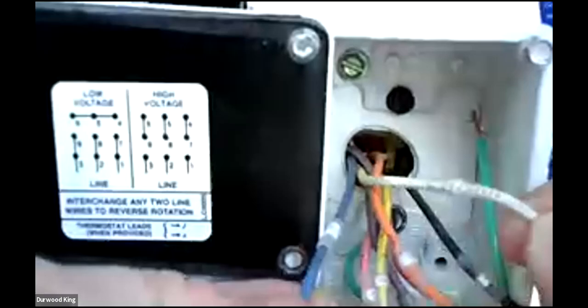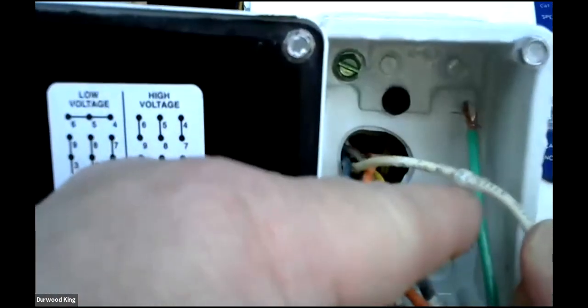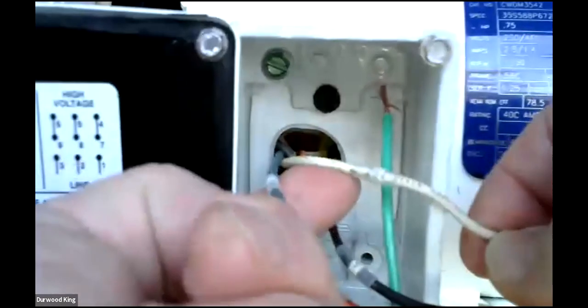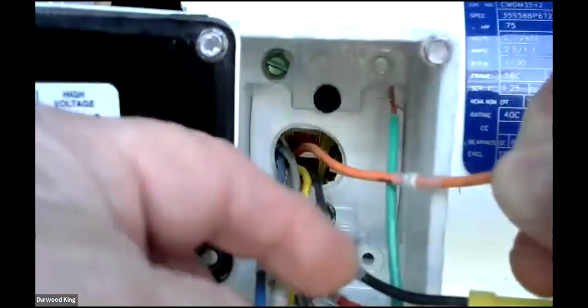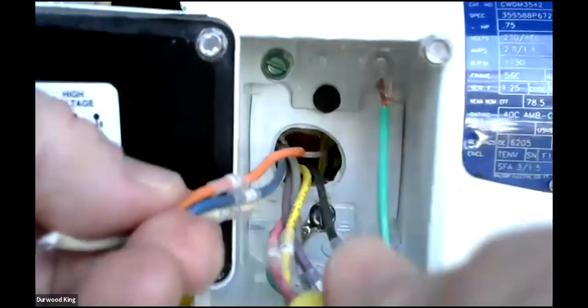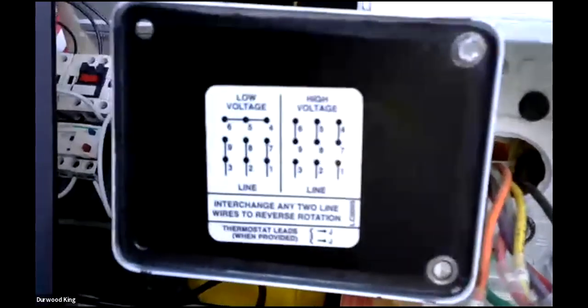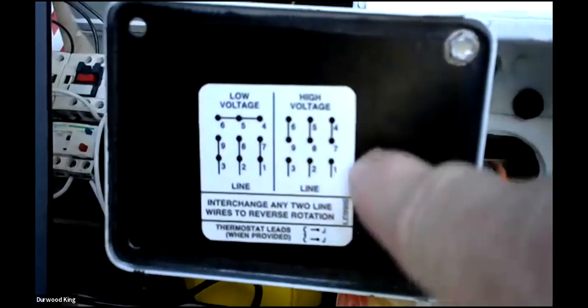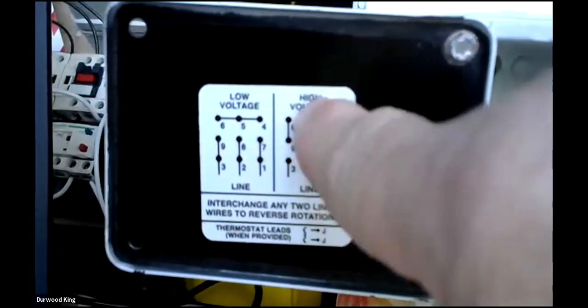And your two right there. And that's really small. You probably can't see that. You can see it a little bit. That two goes to the second leg on the starter. That three right there goes to the third leg on the starter. So you have 1, 2, and 3 single legs going to the starter, and then the rest of it is going to be pairs. So you have a pair that's a 4 and 7 with a wire nut, a 5 and 8 pair, and a 6 and 9 pair. So let's come over like this, and let's take a look at the pairs.